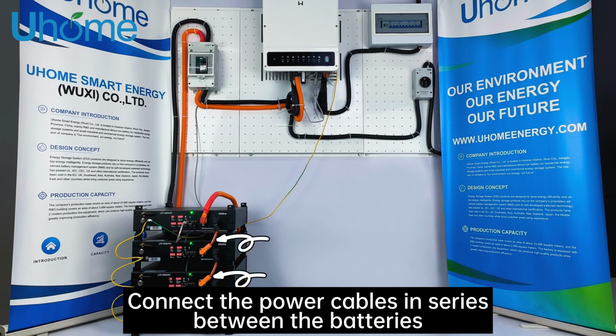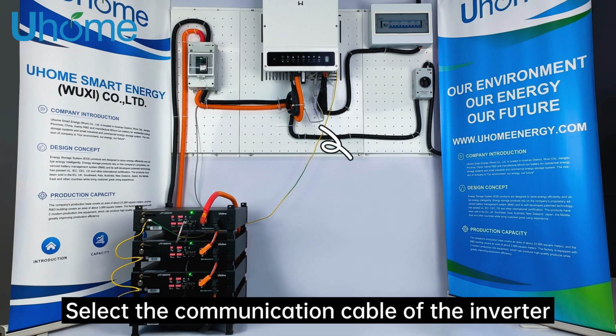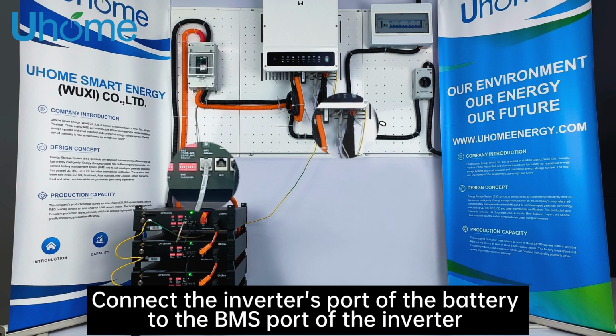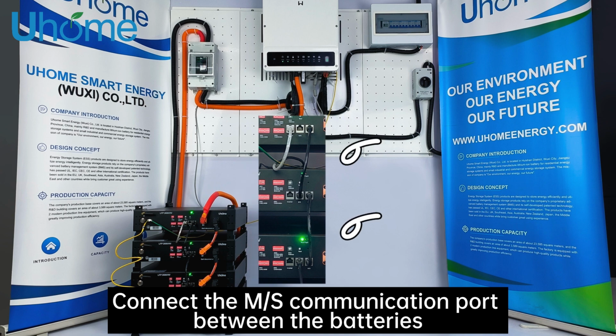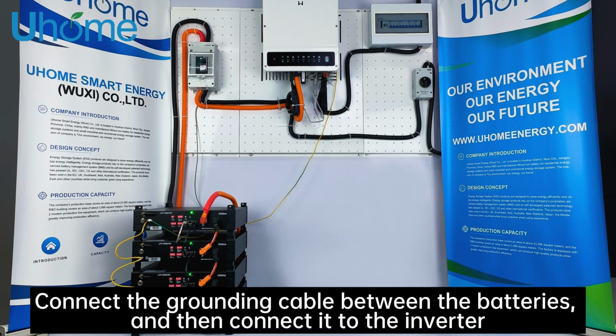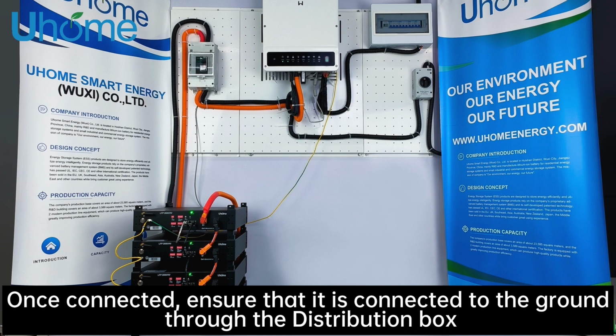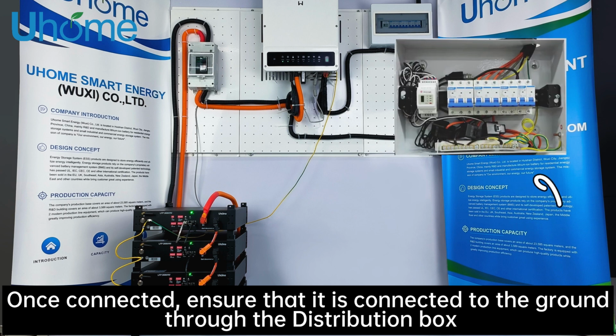Connect the power cables in series between the batteries. Select the communication cable of the inverter. Connect the inverter port of the battery to the BMS port of the inverter. Connect the M/S communication port between the batteries. Connect the grounding cable between the batteries, and then connect it to the inverter. Once connected, ensure that it is connected to the ground through the distribution box.